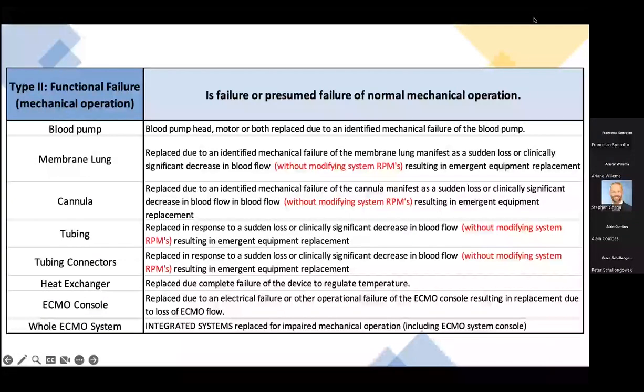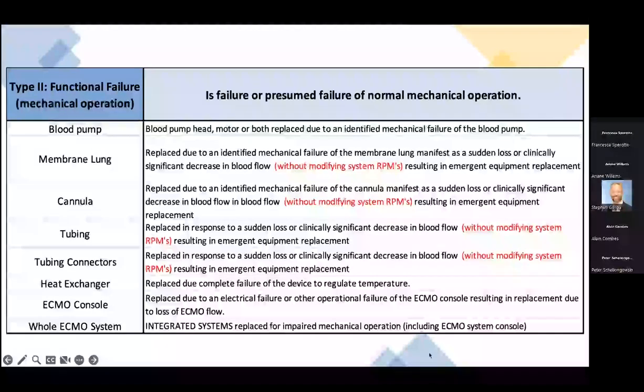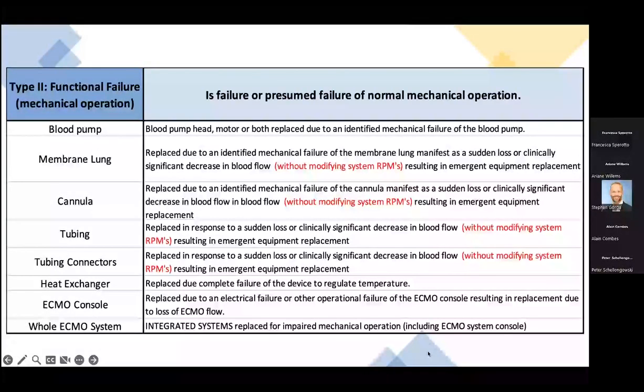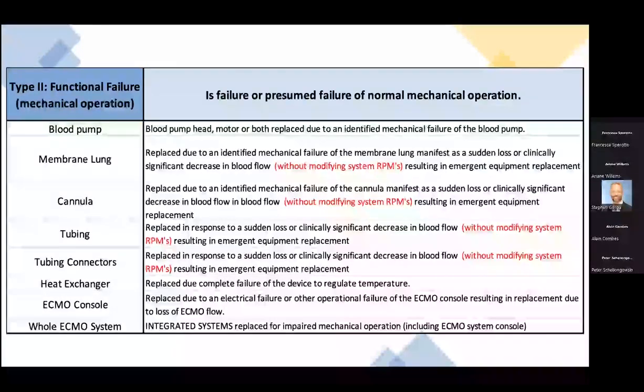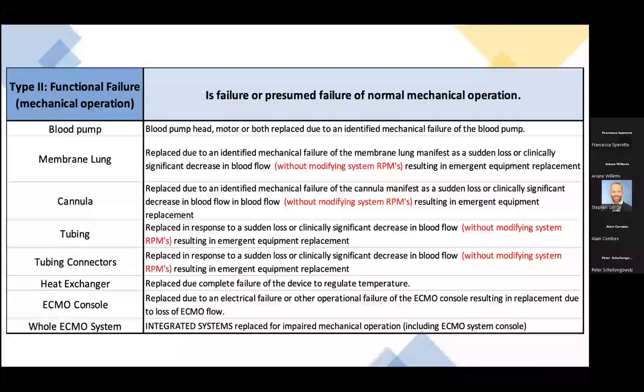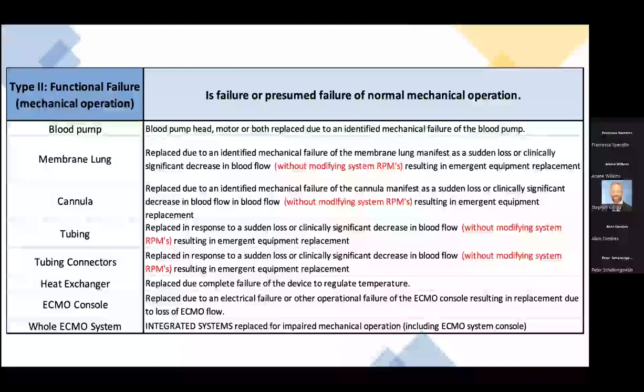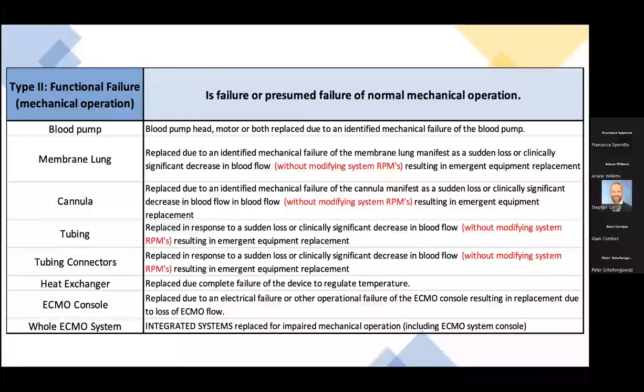Heat exchanger is replaced due to complete failure of the device to regulate temperature. The ECMO console is replaced due to an electrical failure or other operational failure of the ECMO console, resulting in replacement due to lost ECMO flow. An example here would be a knob that is not able to dial or a screen that you are not able to modify. Whole ECMO system, again, is related to the integrated system, replaced for impaired mechanical operation, including the ECMO system console in some of them.